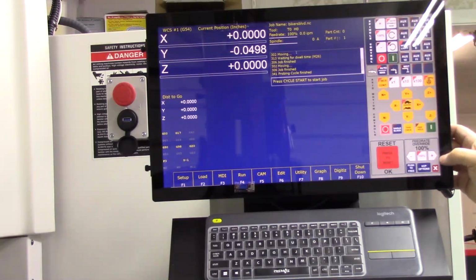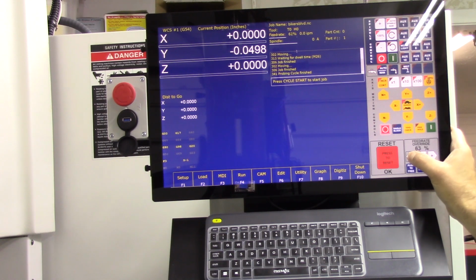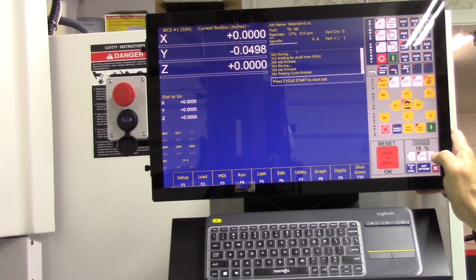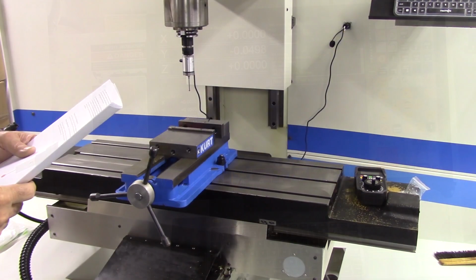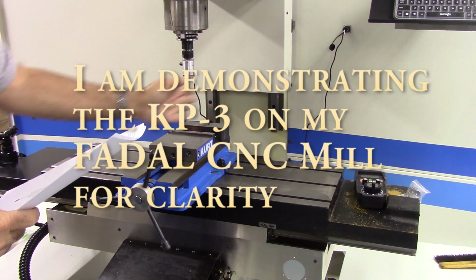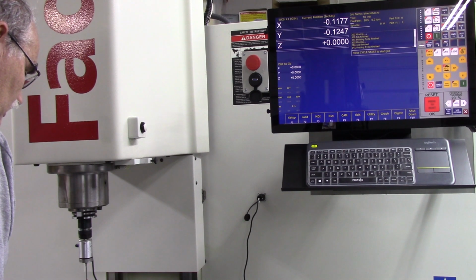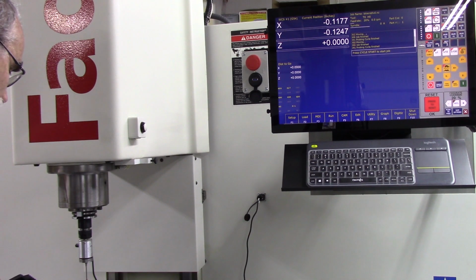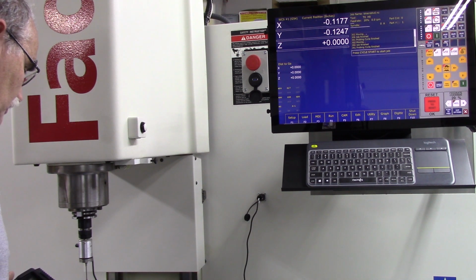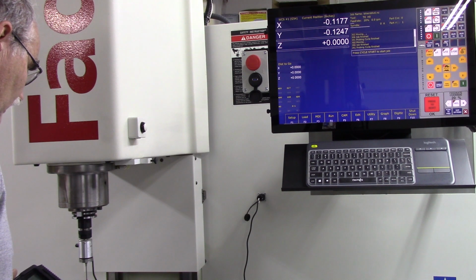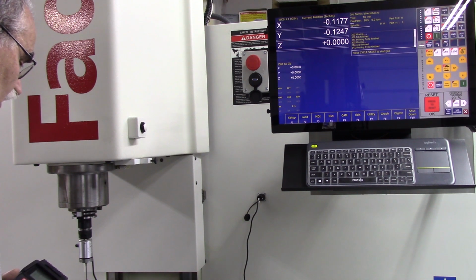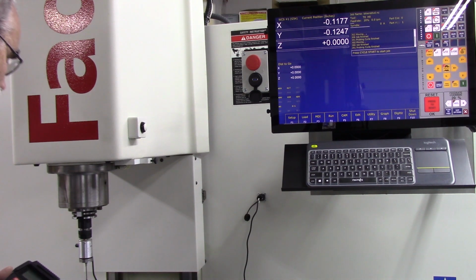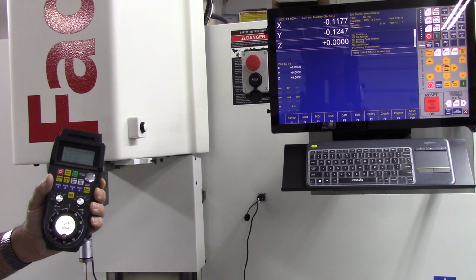To manually test a touch probe using an automatic probing cycle, turn down the feed rate override to 10 or 20%. So let's turn down the feed rate to 20%. There we go. Position the touch probe in the center of the XY travel of the machine tool. So my machine is currently set halfway in X, halfway in Y. With the probe in clear space, start the center bore probing cycle. The probe will begin to move to seek out the edges of the bore at the quadrants. At this slow speed, you'll have plenty of time to trip the probe with your fingers to verify that it is working. No need to complete the probing cycle. Cancel at any time once the probe functionality has been verified. So what I'm going to do is I'm going to use the wireless MPG to start that probe cycle.